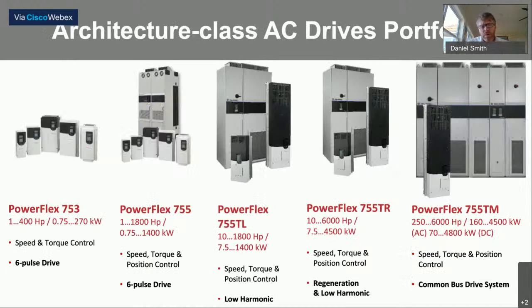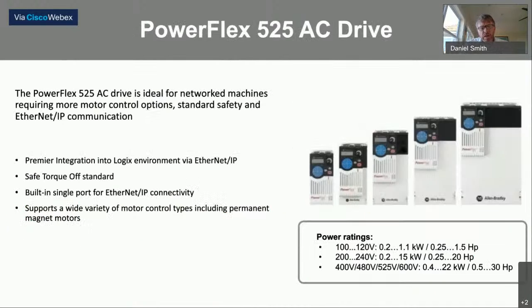Well, one drive I didn't talk about, back up one more, please. The 527 drive, again, looks just like this. The biggest difference between the 527 drive and the 523 and the 525 is it is not a standalone drive. It is only controlled via Ethernet, and it has to be integrated with a CompactLogix or ControlLogix platform. The motor ratings, horsepower ratings, and temperature ratings are all the same as the other 520 series drives. Next slide, Travis.